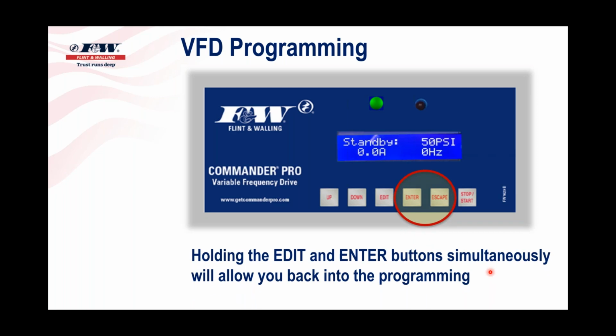So in order to get into the drive from now on, after you've initially programmed it, and I've got my circle up here wrong, folks. Last time I did this, I noticed it, and I never changed it. It says you should hold the edit and enter buttons. That red circle needs to move to the left 1 tab. But you're going to hold the edit and the enter buttons simultaneously. And this is going to allow you to get back into the programming.